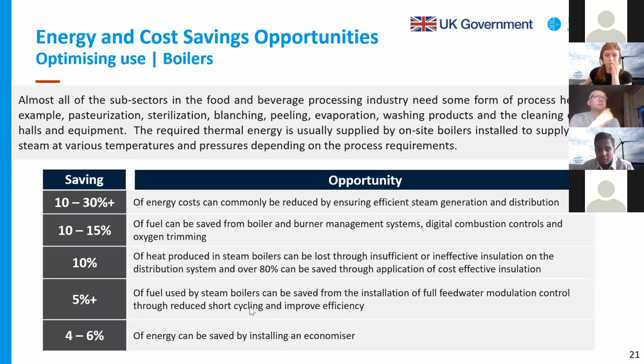And typically 10% of the heat is lost through ineffective insulations. The majority of this can be saved by using cost-effective insulation material and periodic steam surveys to measure insulation heat loss. Roughly 4 to 6% can be saved by installing an economizer to reduce stack temperature and use some of the waste heat.